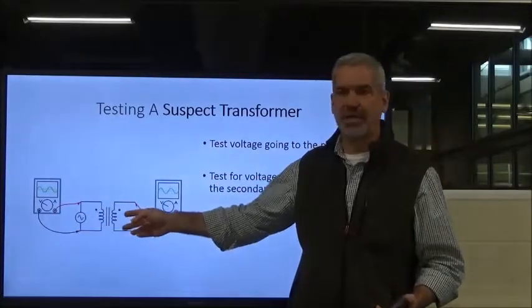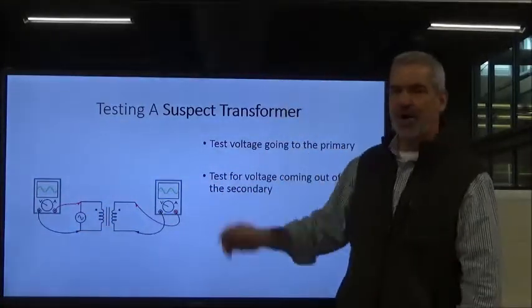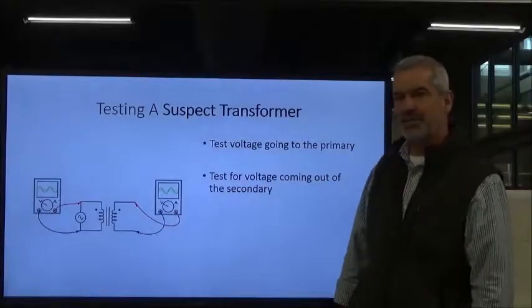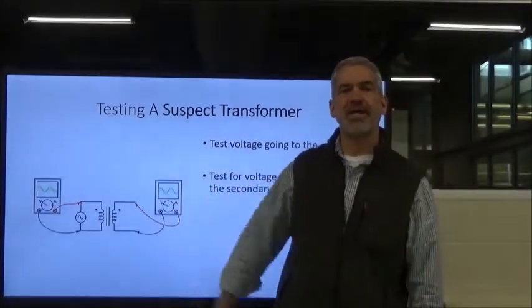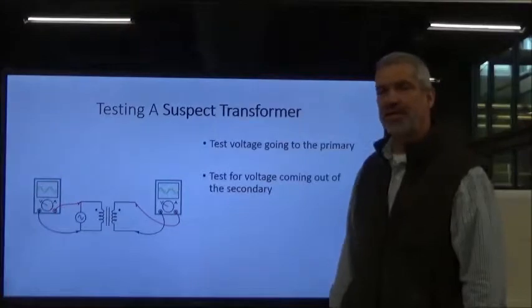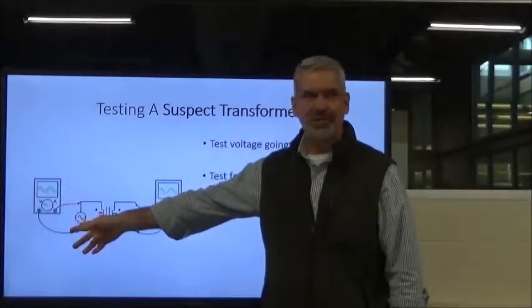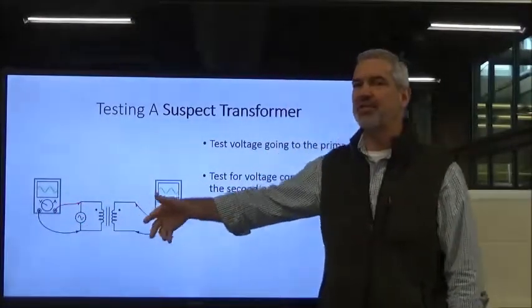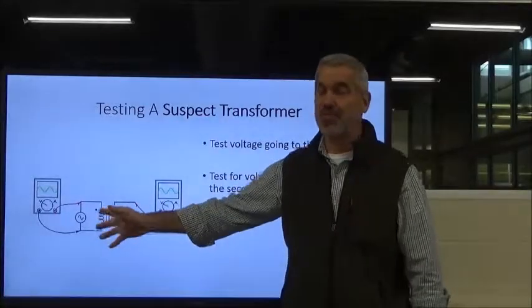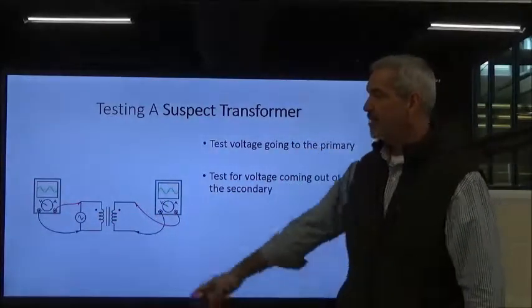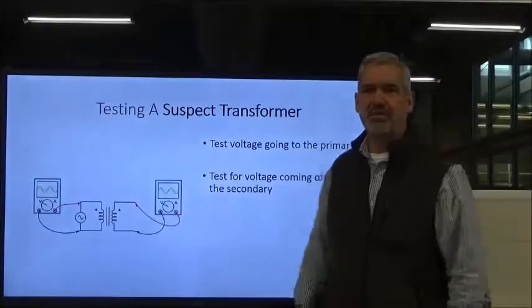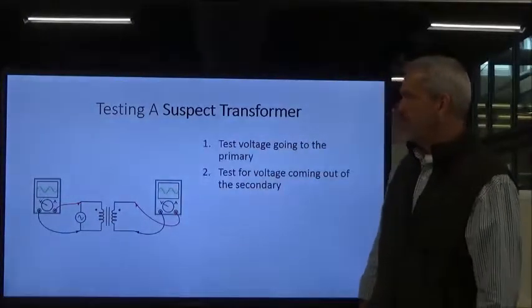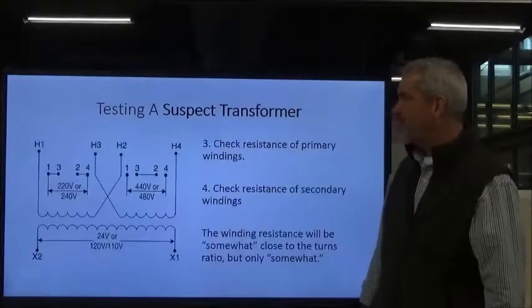A lot of times students will say, "I've got no voltage, so it's got to be that the windings on the secondary are bad." Well, no, not necessarily. Or they'll say, "The windings have got to be bad on the primary side." No, not necessarily. Find out if you've got voltage first, okay? I've seen voltage go out a lot more than I have transformers. Now, transformers do fail, but make sure you've got voltage. That's the first thing you want to do, okay? You want to check and make sure you've got voltage coming out of the secondary.